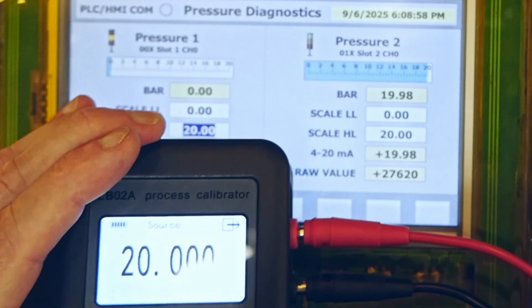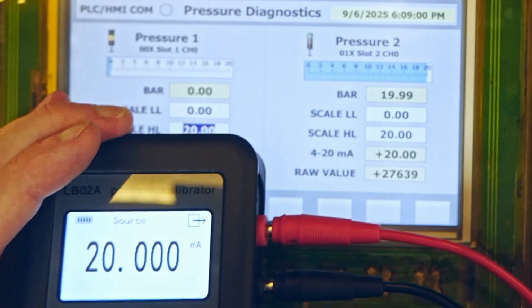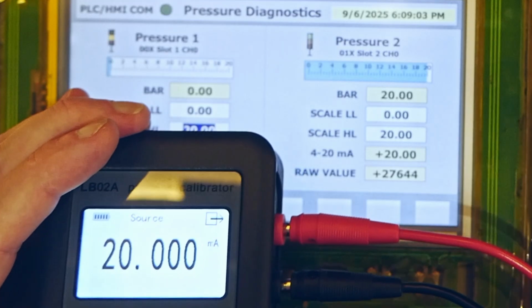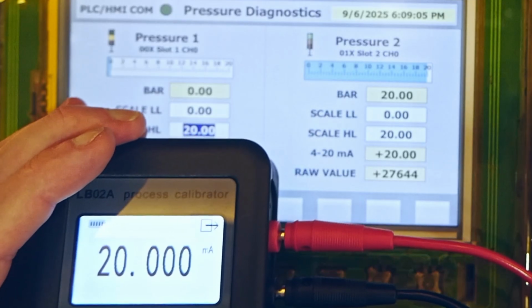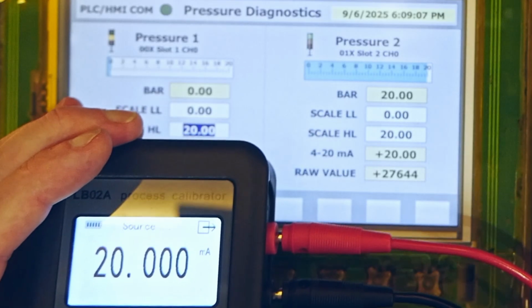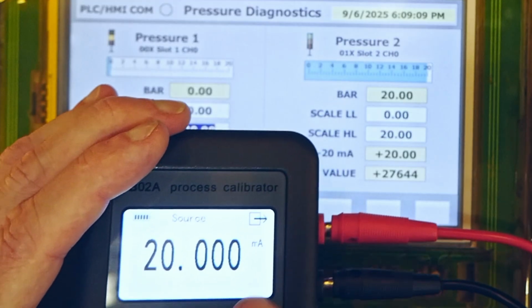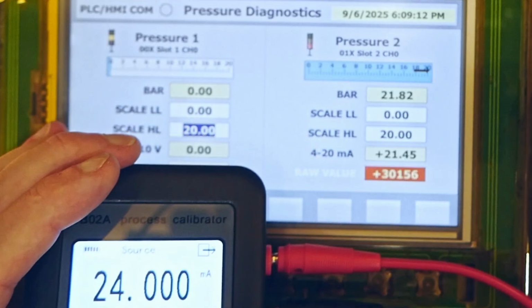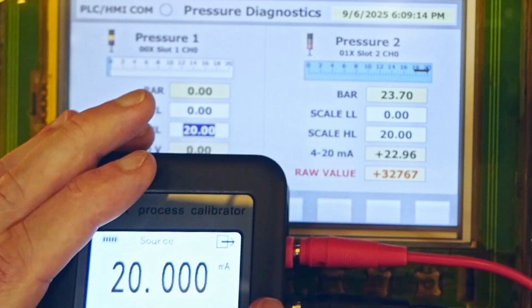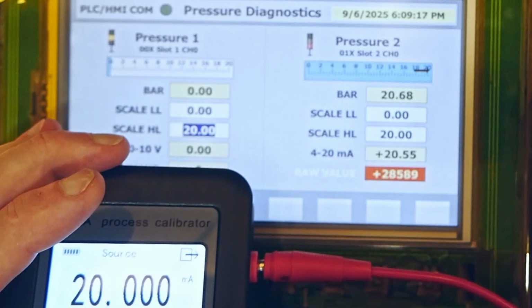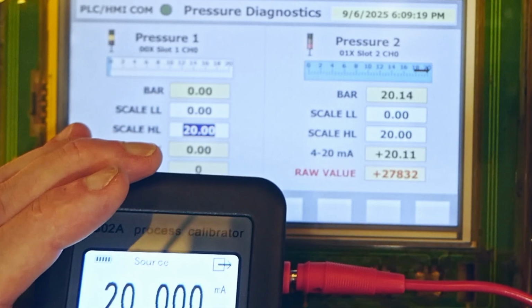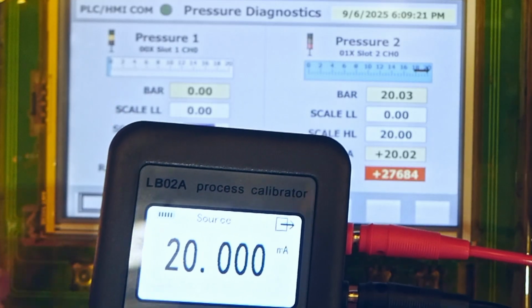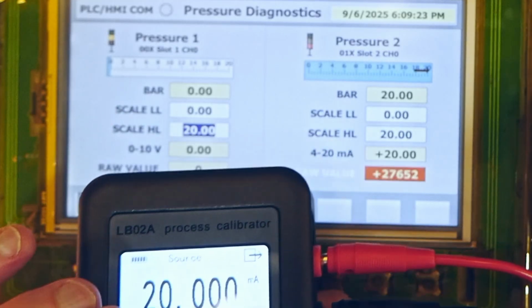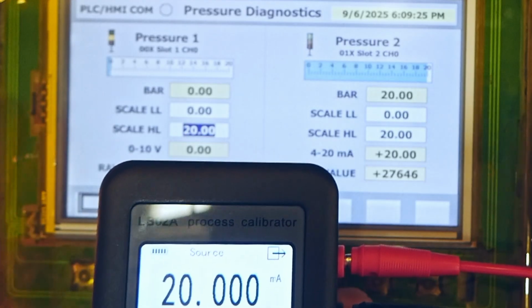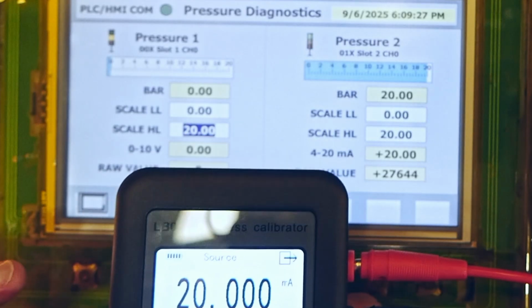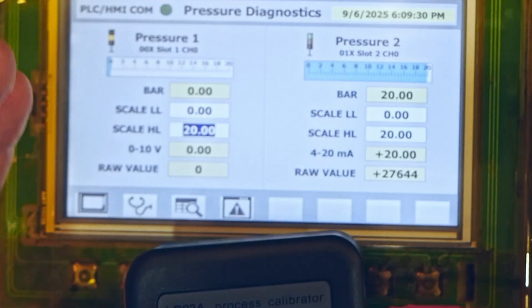It kind of ramps up. It doesn't jump straight to this, let's say from 16 milliamperes to 20. It kind of ramps up. But again, we can, for a short period of time, do a crash test, you know, see if we will get alarm, if our system will work in this condition. So we can test our system with this.